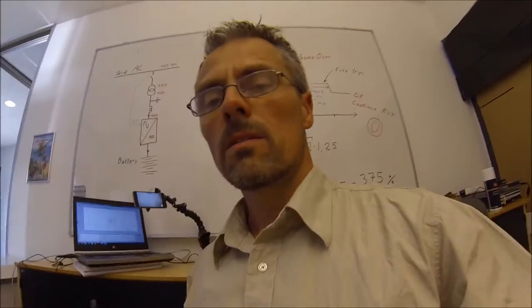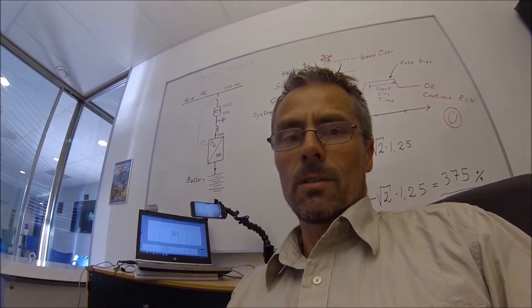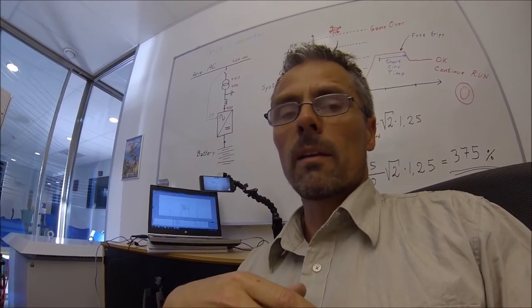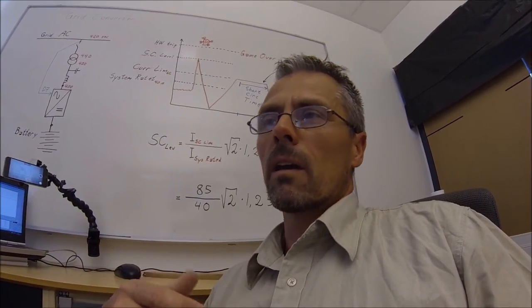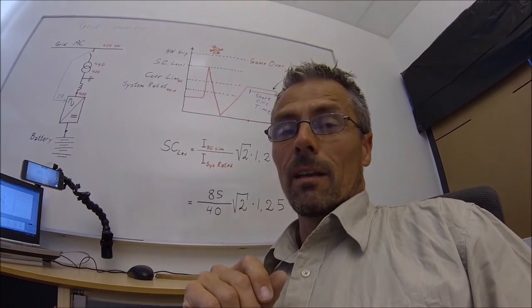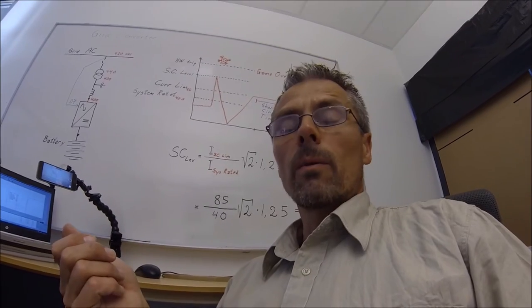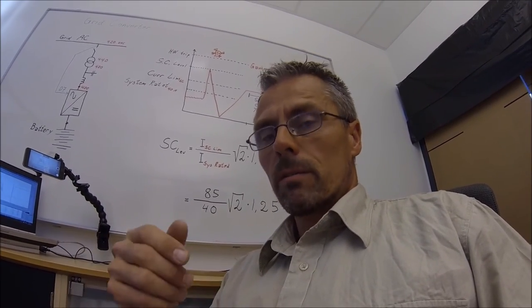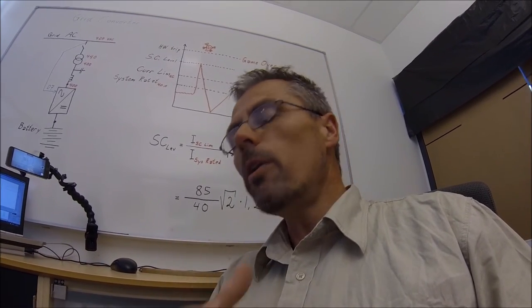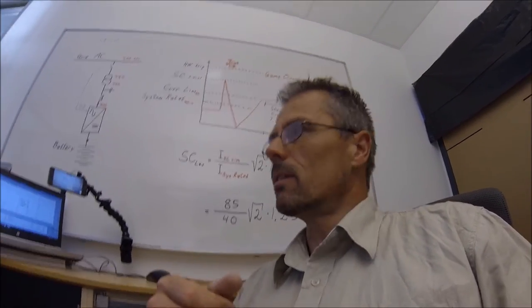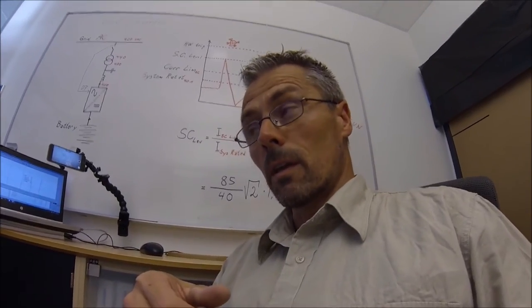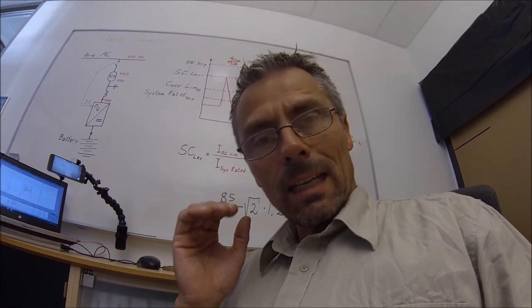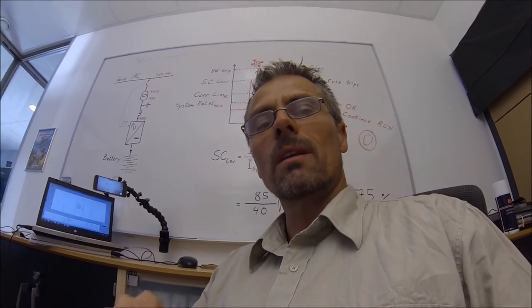So this is selectivity with a frequency converter which is a huge difference when you use a frequency converter with motor control for supplying a grid. If you use a regular motor control for supplying a grid like a shore power then you don't have this functionality. And at best you will trip the drive and you will stop from supplying voltage but you could also have the possibility that you sit there feeding into a short circuit because it's undefined what's happening with the fuses and the selectivity in the system. So this is one of the reasons you should use a grid converter when supplying a distribution system. There is selectivity, you can predict how it behaves when there is a short circuit in the system.